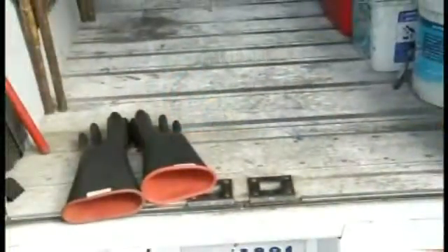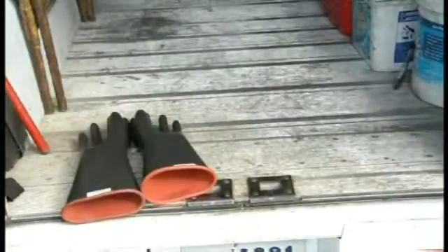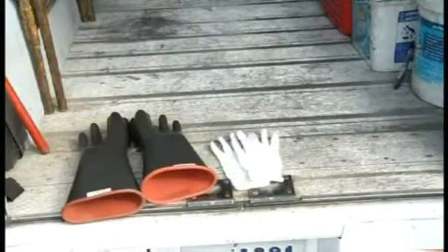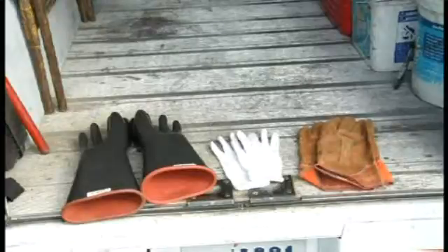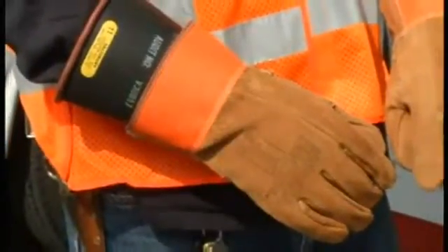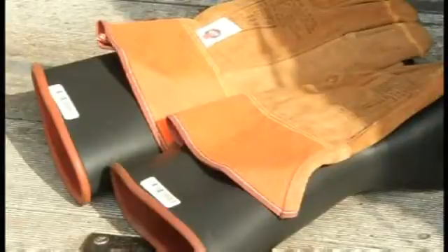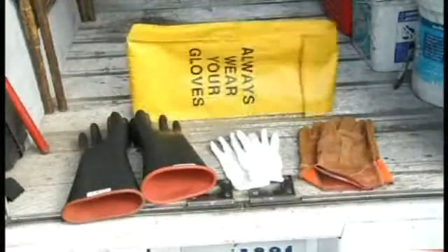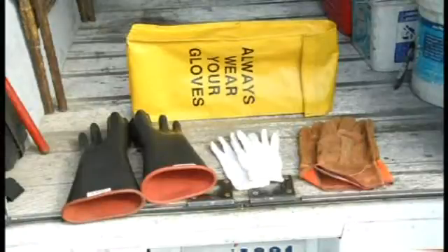Each set of insulating gloves includes 2 insulating gloves, 2 cotton liners, 2 leather protectors. Leather protectors are never to be used as work gloves. Leather protector gloves must only be worn with insulating gloves. Gauntlets of leather protector gloves must be 2 inches shorter than insulating gloves. 1 storage bag. Do not place anything in the storage bag other than the insulating glove set.